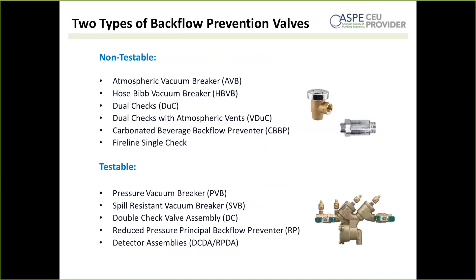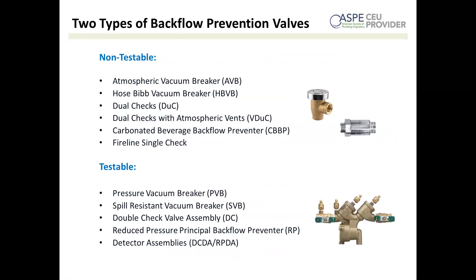One way of grouping backflow preventers is testable versus non-testable. Testable is desirable because you can check functionality, but these devices are typically larger and more expensive, which can be overkill. Many jurisdictions don't require residential containment backflow to be testable due to the cost to the homeowner, but will require testable backflow on commercial containment. North American building codes typically require testable devices to be tested when installed, when repaired, and annually to ensure proper function.